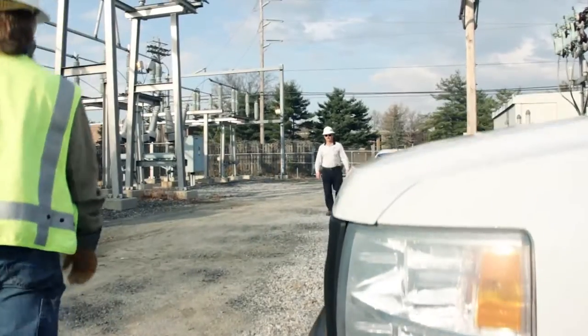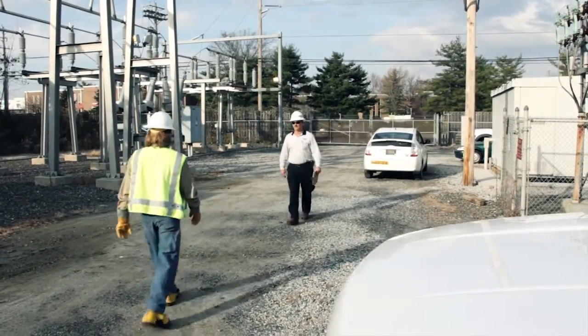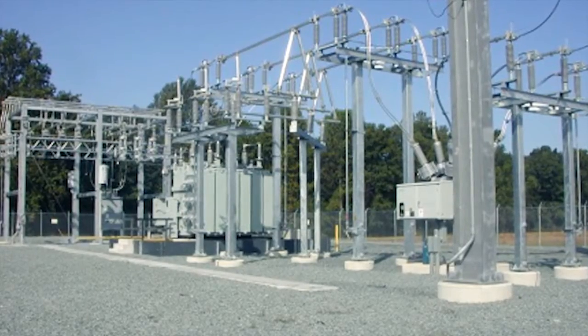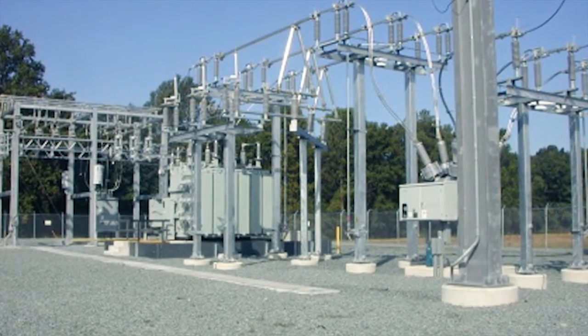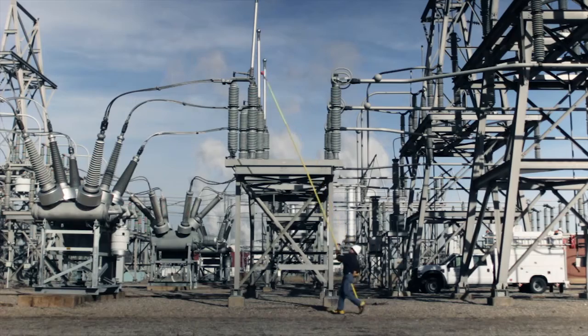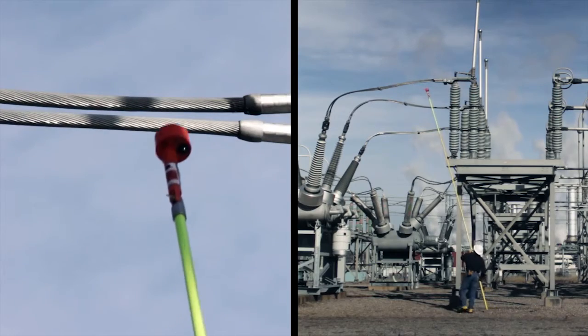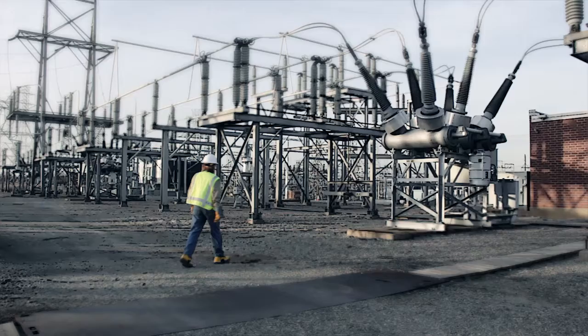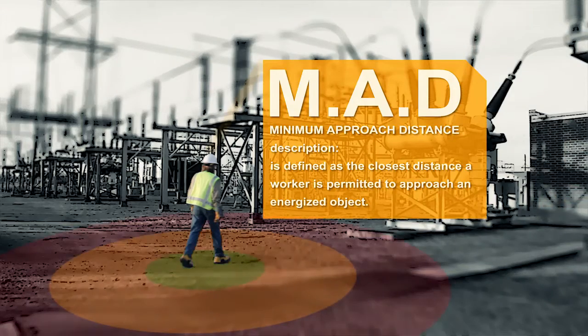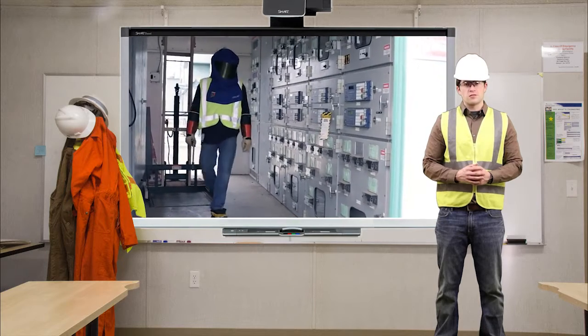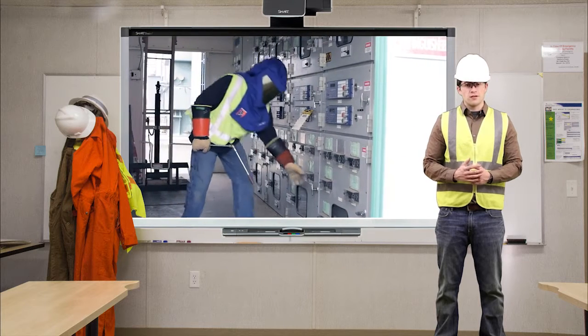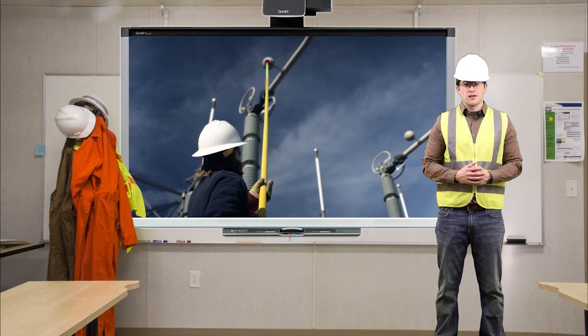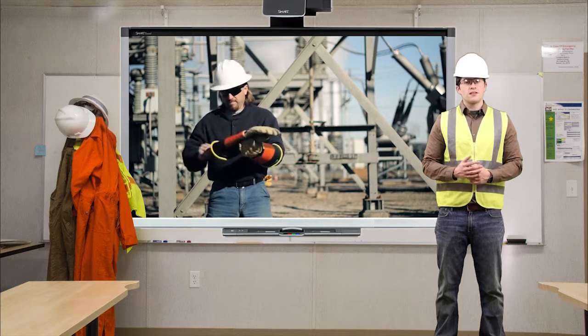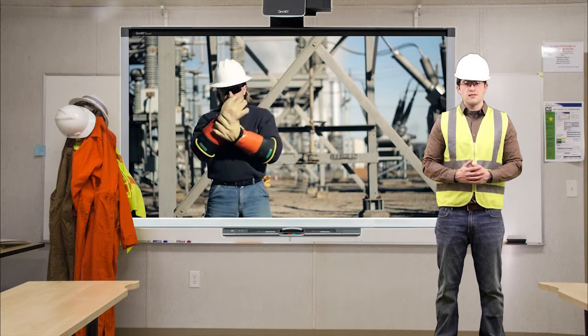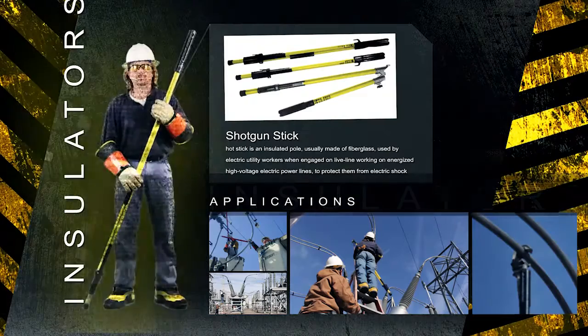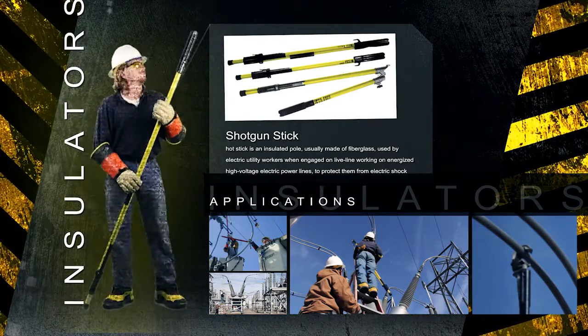In order to be qualified to enter a substation, you must be competent in the following: the skills and techniques necessary to distinguish exposed live parts from other parts of electric equipment, the skills and techniques used to determine the nominal voltage of exposed live parts, maintaining a minimum approach distance, and, for those entering a substation to perform electrical work, the proper use of special precautionary techniques, personal protective equipment, insulating and shielding materials, and insulated tools for working on or near exposed energized pieces of electrical equipment.